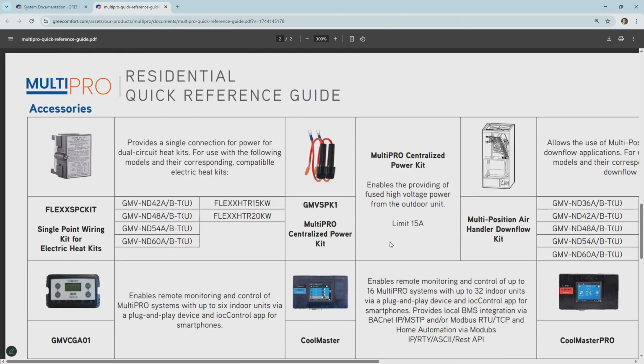Now, it's limited to 15 amps. So what I would tell you is look at your submittals. It depends on what indoor units you're using. Most of the heads are probably only going to pull an amp or so. You only run a blower and a board. But then we also have to look at our overall power supply to that outdoor unit, and make sure we're not loading that all the way up to 15 amps, because then we don't have enough power for the condenser and all those indoor units. So probably no more than 4 is what I would tell you on a wall mount or a cassette or something like that. Okay.